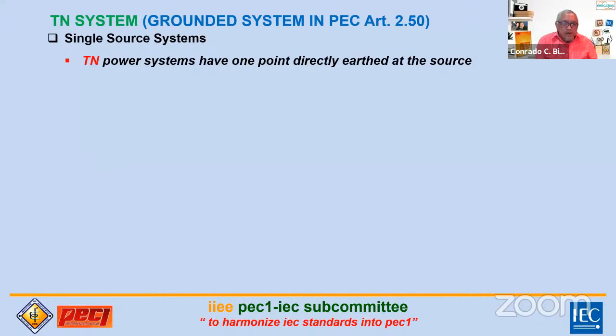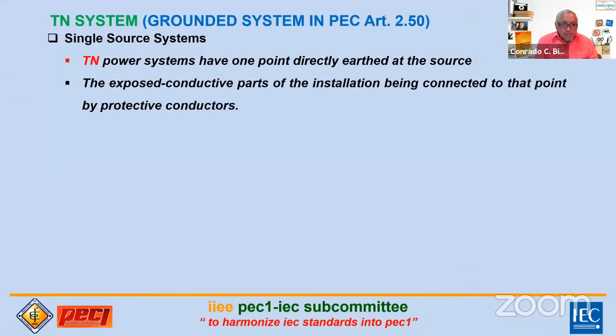TN system, IEC, grounded system naman dito sa PEC natin. One power system having one point directly earthed at the source, yung source natin, yung transformer. So the exposed conductive parts of the installation are connected to that point by protective conductors.